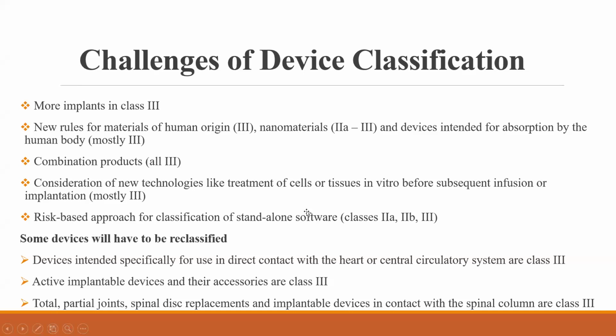And for example, in case of SaMD, like software as a medical device, they were classified as class 2A, 2B, and 3. And this also need to be addressed. And some of the devices also need to be reclassified, because in daily, in our work as well, we do come across sometimes the particular class 3, class C device changes to class B device, and class B device changes to class C. It depends upon the regulatory requirement. So as the regulatory is a dynamic field, it's a dynamic work. We always need to edit that particular technical documents or declaration of conformity, basing upon the requirements of the particular standards being followed by that particular country.